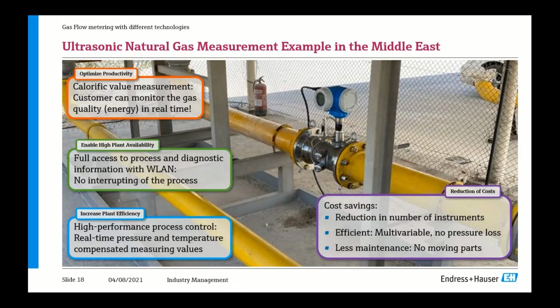So with this new electronic ultrasonic gas flow meter, which is not only an ultrasonic gas flow meter but also includes temperature, pressure, and a calculation facility, you can measure not only flow but also the calorific value. That is very important for the customer, but also, based on a parameter like, for example, the speed of sound, the customer can monitor the gas composition or the quality of the gas. To gain trust in the meter, he is yearly using intensively the diagnostic capabilities, and for that he doesn't even have to leave his office. He can do that using the wireless LAN and using a tablet or a computer. No interruption of the process. You can run full diagnostics of the device. And in the end, this customer is replacing not only a turbine, but also a temperature sensor, a pressure sensor, and a calculation box with one single device. And there is no maintenance, there are no moving parts, and he has much more information from this measuring point. Next slide, please.